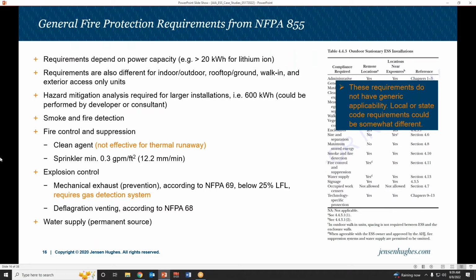Back to standards real quick: they should have smoke and fire detection, fire control and suppression. As I mentioned, clean agent systems like Novec or FM200 do a great job extinguishing flames, but they're not going to help cooling a battery that's in thermal runaway. That's why you've got to put water on it.